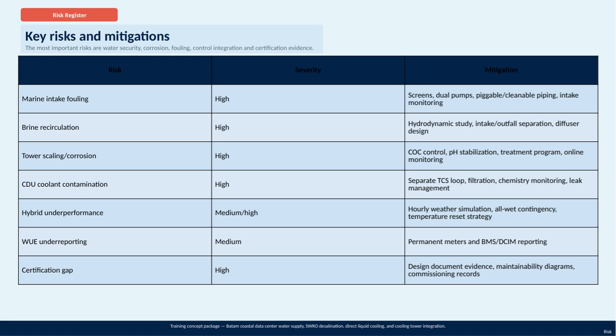For water use efficiency underreporting, considered a medium risk, we're installing permanent meters and integrating monitoring into the building management and data center infrastructure management systems to ensure accurate reporting. Lastly, the certification gap is a high-risk area. To address this, we're maintaining thorough design documentation, developing maintainability diagrams, and keeping detailed commissioning records to provide clear evidence for certification. This comprehensive approach within the training concept package, covering coastal data center water supply, SWRO desalination, direct liquid cooling, and cooling tower integration, ensures that we proactively manage risks and maintain system reliability.